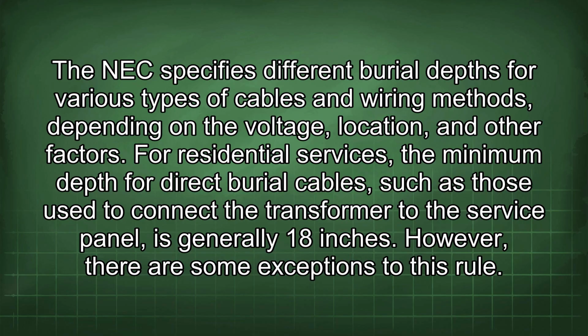The NEC specifies different burial depths for various types of cables and wiring methods, depending on the voltage, location, and other factors. For residential services, the minimum depth for direct burial cables, such as those used to connect the transformer to the service panel, is generally 18 inches. However, there are some exceptions to this rule.